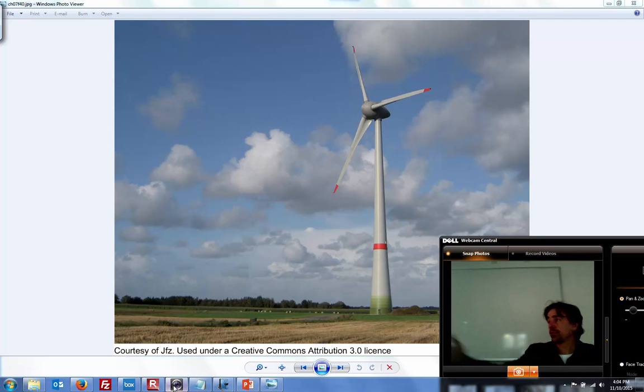And we were even talking about that earlier when Zoe was in the room here. So let's just imagine the wind is blowing from this direction, right? So I've got this big tower flexing back and forth, back and forth, back and forth. Well, where would you expect the crack to develop? It's going to happen on the front or the back, right? It's going to open up and split. Well, what was interesting about this case, he was seeing cracks on the sides. And knowing that you've got the prevailing wind flexing the thing this way, back and forth, he could not for the life of him figure out why the sides were cracking. Any guesses?